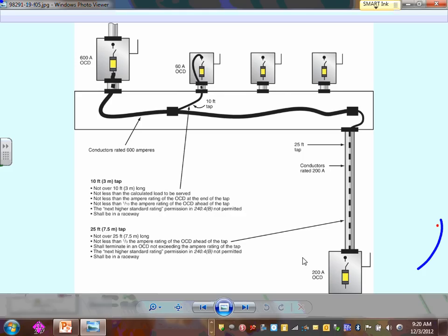Ultimately, the load, how much you're going to go by the load, right? So right now we're tapping this conductor here and tapping this conductor. By the way, why would you use a tap? Cheap equipment. Instead of having a main panel, this is your main panel. 600 amp main panel is right here. A gutter with a bunch of wires and lugs and taps on them. So why would you use a tapping system? Cheaper installation of system instead of using a main panel.